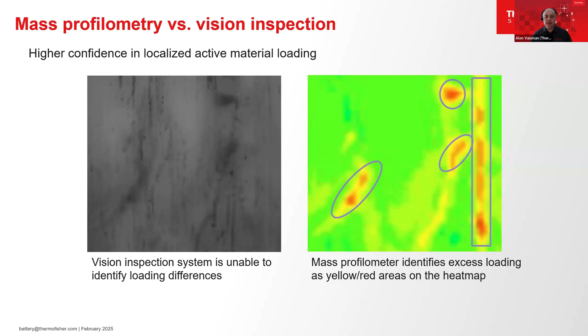To emphasize the unique capability of mass profilometry for detection of loading defects, we performed an experiment where a sample of electrode was measured and the mapping of it is shown on the left. We then took a few flakes of the same cathode material and placed them on top of the sample. You can see these flakes in the middle. They range in size from approximately 1 to 5 millimeters. We then remeasured the sample with the flakes on.